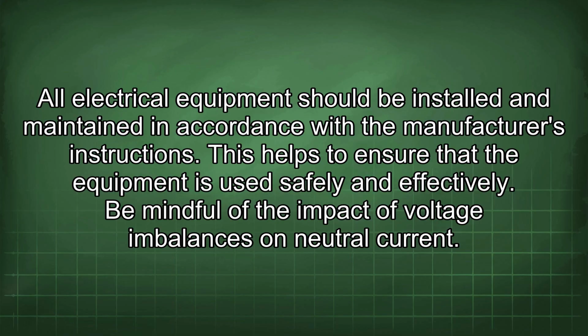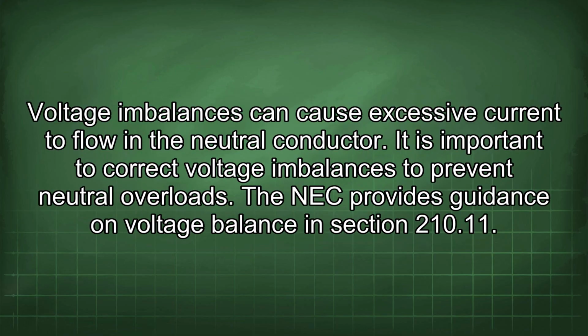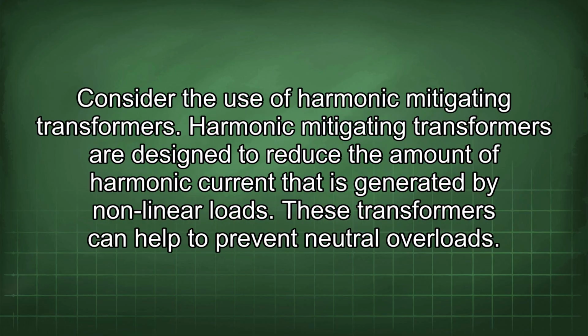Be mindful of the impact of voltage imbalances on neutral current. Voltage imbalances can cause excessive current to flow in the neutral conductor. It is important to correct voltage imbalances to prevent neutral overloads. The NEC provides guidance on voltage balance in section 210.11. Consider the use of harmonic mitigating transformers. Harmonic mitigating transformers are designed to reduce the amount of harmonic current that is generated by nonlinear loads. These transformers can help to prevent neutral overloads.